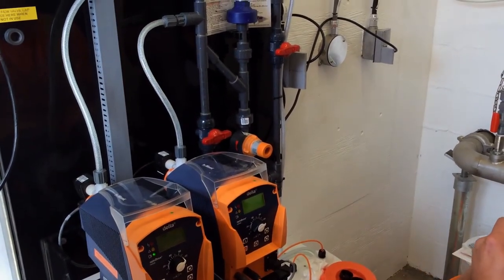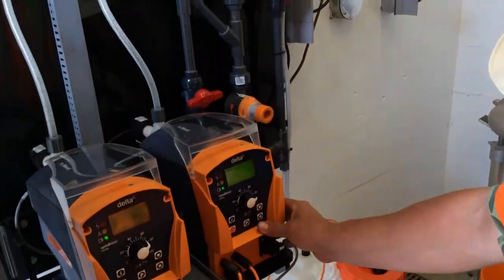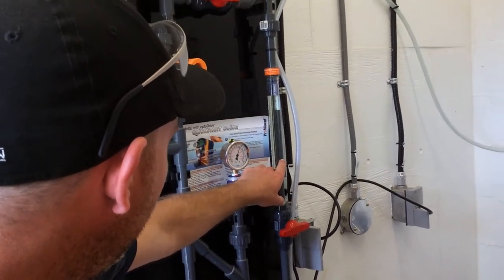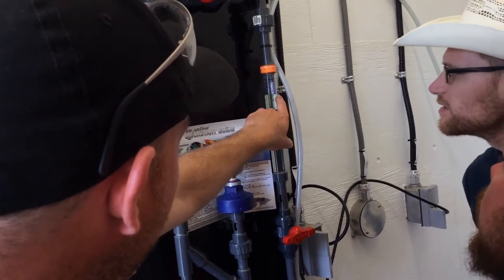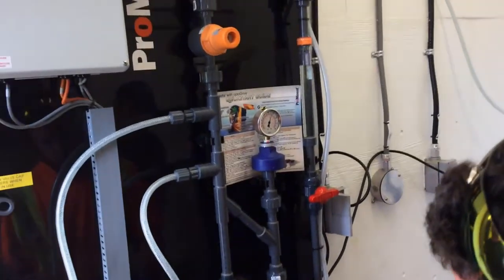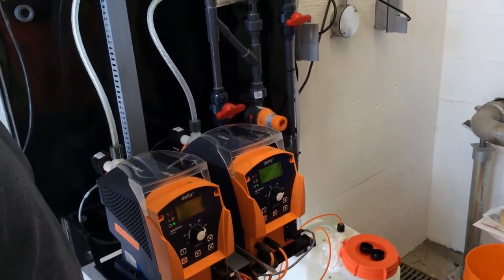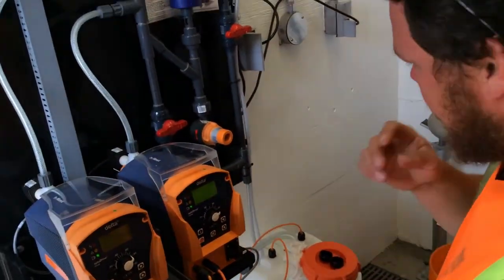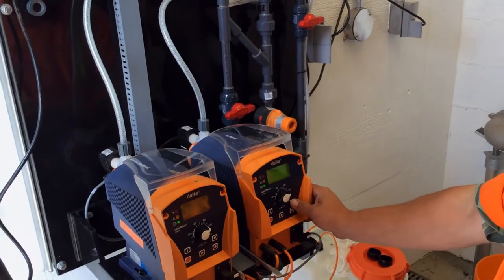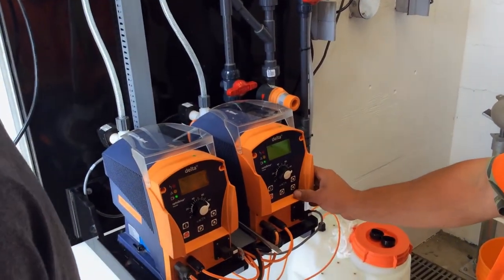Getting up near 90. So anytime you want to press P, go for it. Just press once. And so it's saying, how much did I just pump? So we pumped from 9 up to, what is that, 86. So 86 minus 9 is 77. So I want to put in 77 mils. So it actually thought that it did 71. It's pretty close. 77, press P.